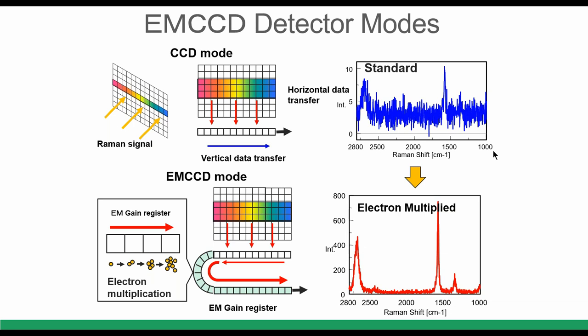The standard detector used in Raman spectrometers is the CCD. But for fast mapping we need an EMCCD detector. The CCD detector can run in different modes — one is the EM (electron multiplier) mode, where a higher voltage is applied and when the signal is registered, the electrons measured in the CCD detector are increased. As a consequence, we have an electron-multiplied signal that increases the intensity of the peaks of interest.